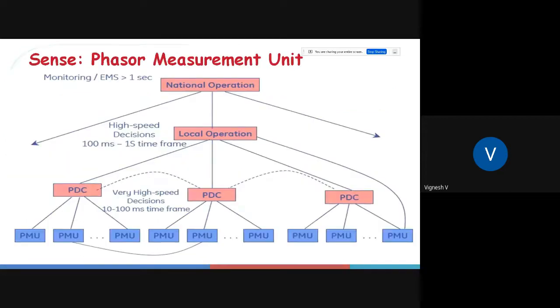Next slide please. So the way it is structured is like, for example, you have various PMUs at the PMU stations. Multiple PMUs report to the PDC, phasor data concentrator, wherein you have data filtering, data time synchronization, time alignment, everything happening at the PDC level. Of course, PDC can also do some of the applications by itself - it has some intelligence to do the application, and the PDC reports to the local or regional operation. From the regional operation, it goes to the national operation, which is wider and wider.